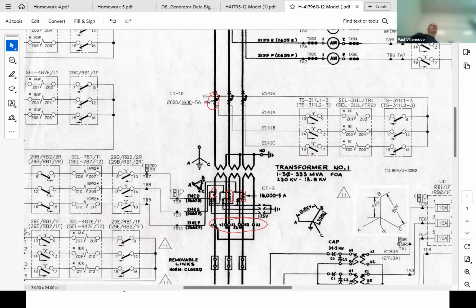These CTs are actually within the physical transformer itself. They're buried in the windings. So normally when you have a delta connected load, you monitor the current like that, right? They're actually monitoring those as phase currents in this case - they're not getting line currents, they're getting phase currents.